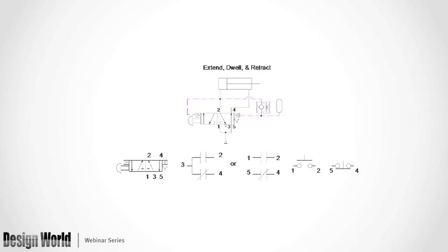It's pushing the whiteboard eraser with a cylinder. It's a rodless cylinder going across the top of the whole board. It's pushing, but it creates a pressure here, and that pressure comes back and holds the pilot energized, just like an electric holding relay. I push the button and it latches in.